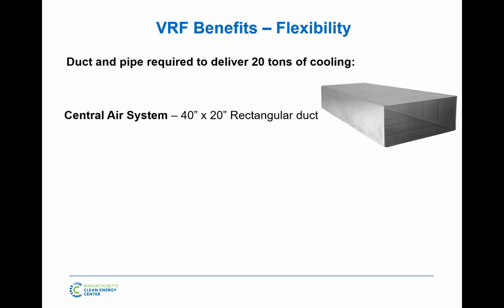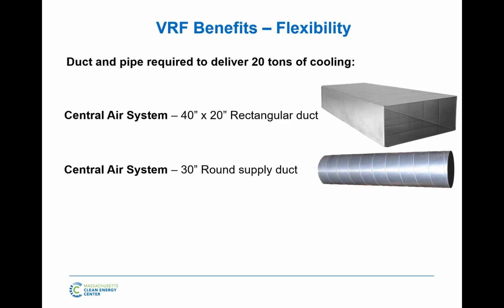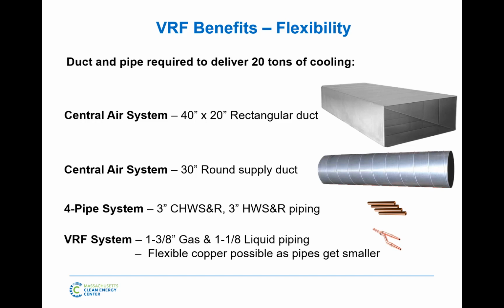The next thing we talked about a little bit is the sizing and the flexibility of the system. This is just a visual example of 20 tons of cooling, for example, with air. So picture this as your VAV system, it would be this big. Your central air system, similar idea. Your chilled water system, you might use a 4-pipe system, especially if you want to give independent heating and cooling. With a chilled water system, you need a 4-pipe system. That could be a water source heat pump. You're going to have these water pipes, 3-inch pipes. All of them are hard copper, plumbing copper. With VRF, you're going to be using maybe 1 3/8, 1 1/8 for 20 tons. That's it. 2 pipes. You get insulation around them, usually 1/2 inch or 3/4 inch Armaflex wall. So if you look up and you see VRF pipes, you're going to see what looks like 2.5 inch black piping.